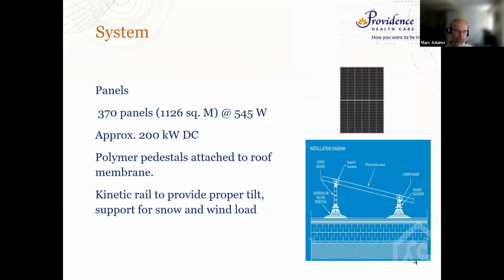The system itself that we installed on the roof: we put in 370 panels at 545 watts each, giving us approximately just over 200 kilowatts of DC collection ability. The roof of the facility was also recently redone over the last year, so we were able to add new pedestals compatible with the membrane that was put on.